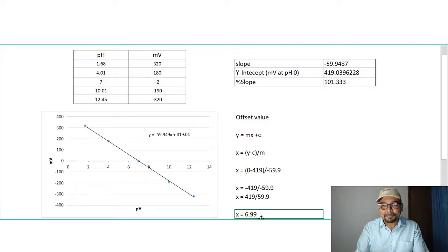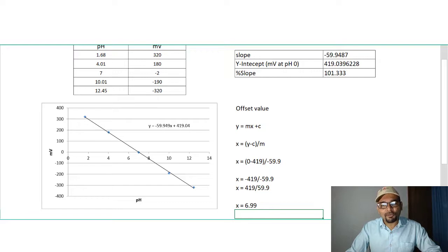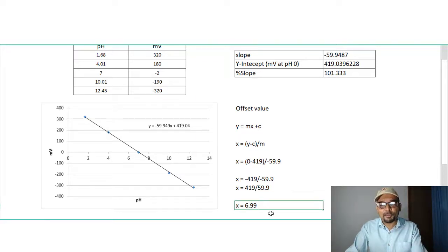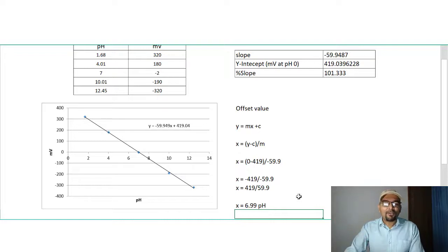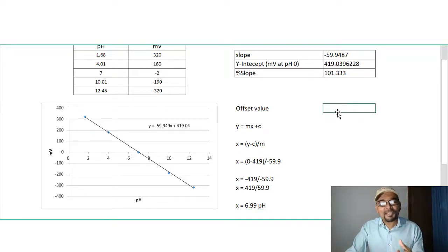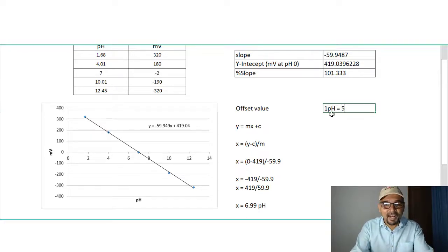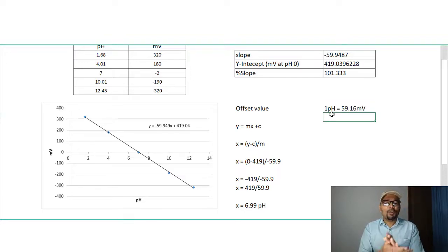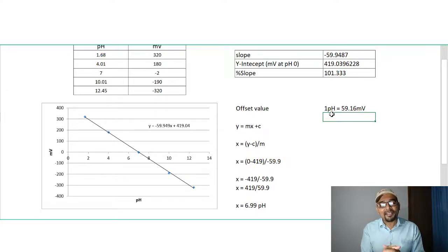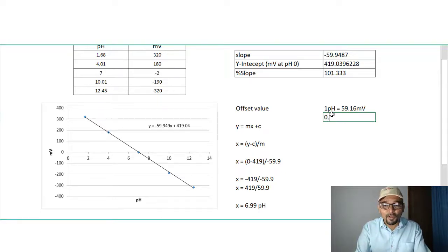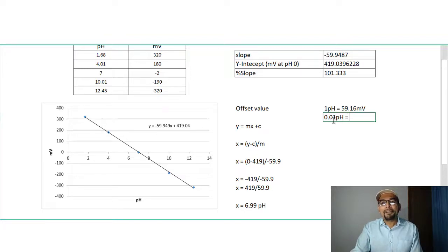The result of 6.99 indicates that our observed calibration line crosses 0 millivolts not at pH 7.00 but at pH 6.99. The offset in pH units is therefore 7.00 minus 6.99 = 0.01 pH units. Since 1 pH unit equals 59.16 millivolts, 0.01 pH units corresponds to 0.01 × 59.16 = 0.59 millivolts.